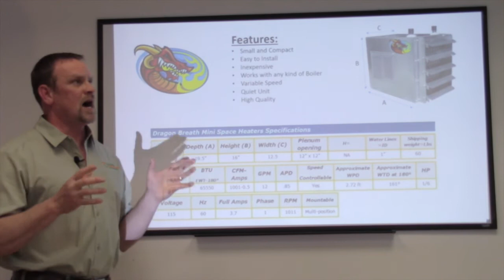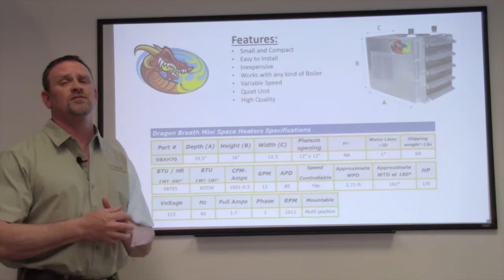To give you an idea of how much it can heat, 70,000 BTUs at 200-degree temperature hydronic water. A house that's about 3,800 square feet that is very well insulated needs about 140,000 BTU to heat the entire house in about the New England area, to give you an idea. So 70,000 should be able to do 1,500 to 1,700 square feet of well insulation. That's a lot of heating for a very small unit. It's very easy to install. It's very inexpensive for what it can do and your options for heating, considering it's a complete unit.